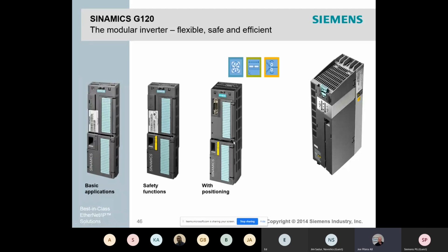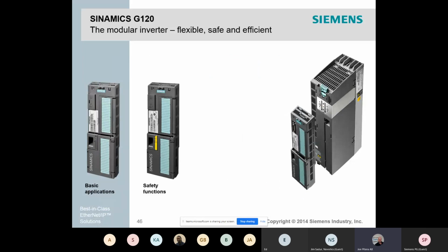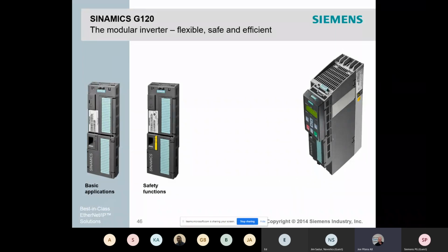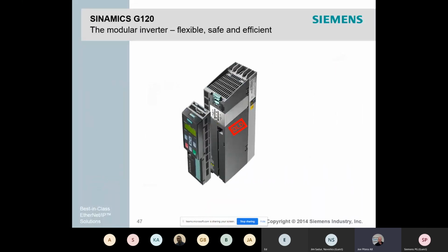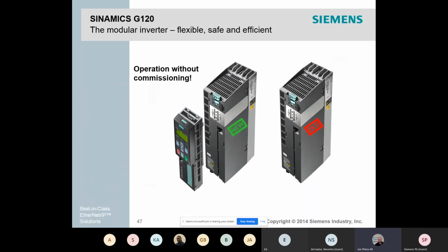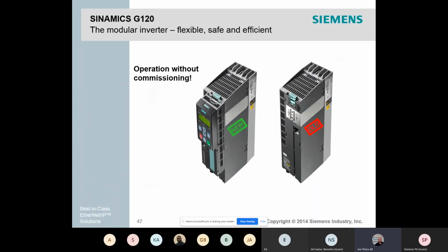In case there's a failure of the power unit, you can simply unclip the control unit, replace the power unit, wire in the three-phase power in and the motor out, and clip on the control unit without even having to remove all the wires to it. Power up the system, and you'll be back and running in no time. No need to even download parameters because the parameters stay in the control unit itself. If an old power module is not working, it can be replaced quickly with a new one. The inverter will operate with the old control unit with no need for commissioning.